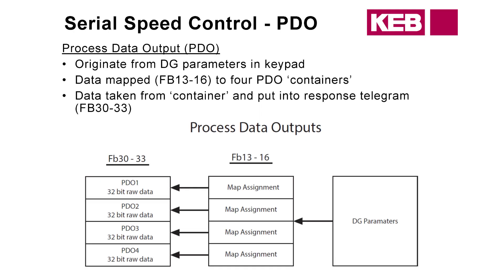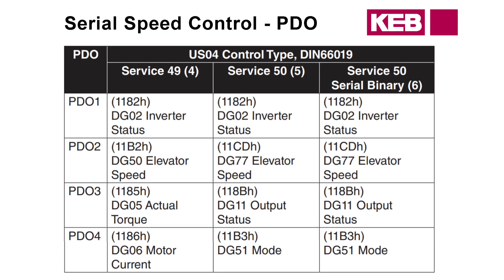Now the controller is looking for some stuff from the drive. It's going to originate in the DG parameters — those are diagnostic parameters, read-only, you cannot adjust them. Basically the same process as before but in reverse: they will be given their correct mapping assignment to which process data output they will be linked to, and ultimately go to the controller. Here are the default values for the PDOs: inverter status, so the controller knows what the inverter is doing; elevator speed; torque output; and motor current.